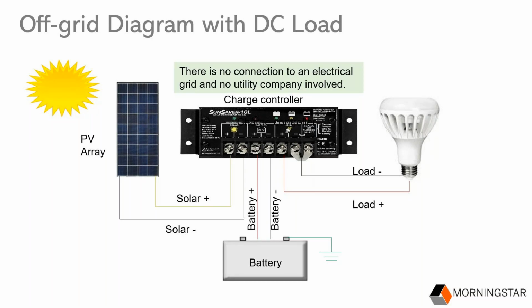You'll notice that the battery is grounded at the negative battery terminal, and this is because all of our controllers have a common negative ground. So it's possible to establish a common negative ground for the entire system—the solar array, the battery, and the load—and this meets NEC code requirements for grounding.